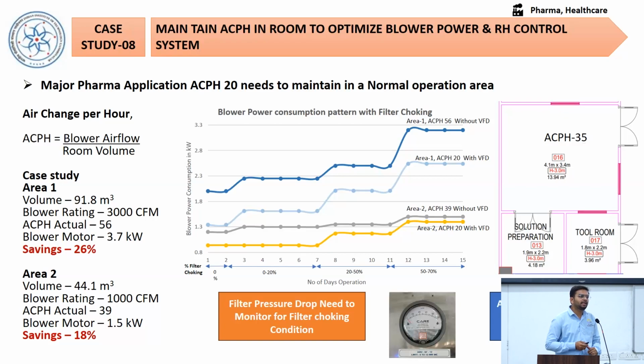We observed that in these industries also, where they are maintaining 56 ACPH and the requirement is only 20. So we recommend not to change the blower, because whenever the filter chokes, a higher capacity blower may be required. We recommend installing a VFD on that blower and monitoring the filter pressure drop.